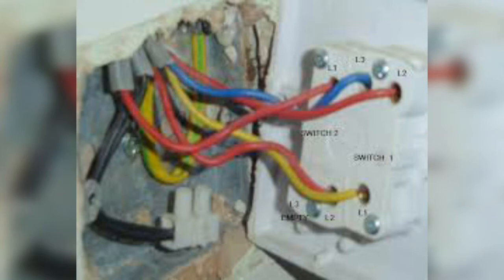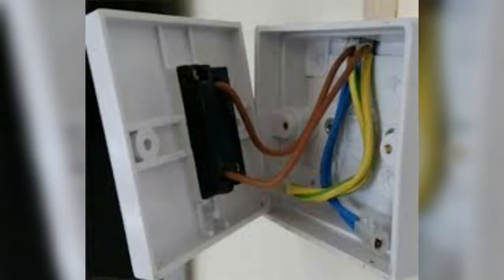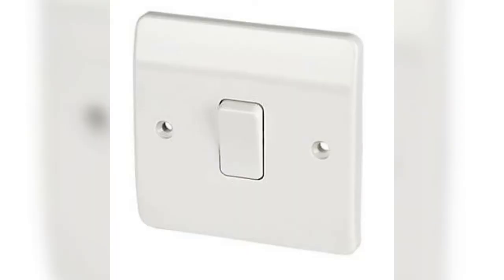To remove these wires, insert the blade of a small screwdriver into the slots under the hole in which a wire is inserted and push in so the wire comes loose. Push the blade of the screwdriver into the slots. Release the grip on the inserted wire.